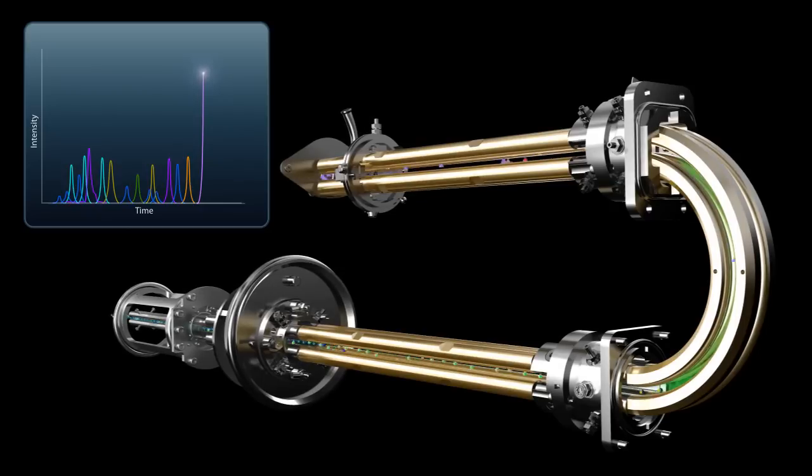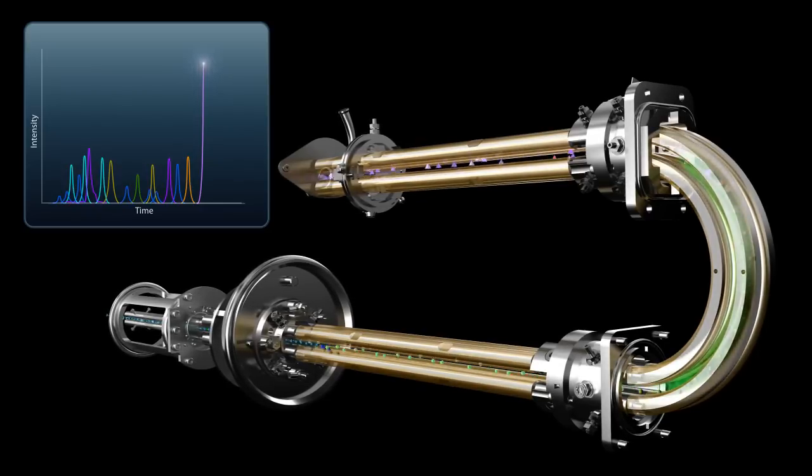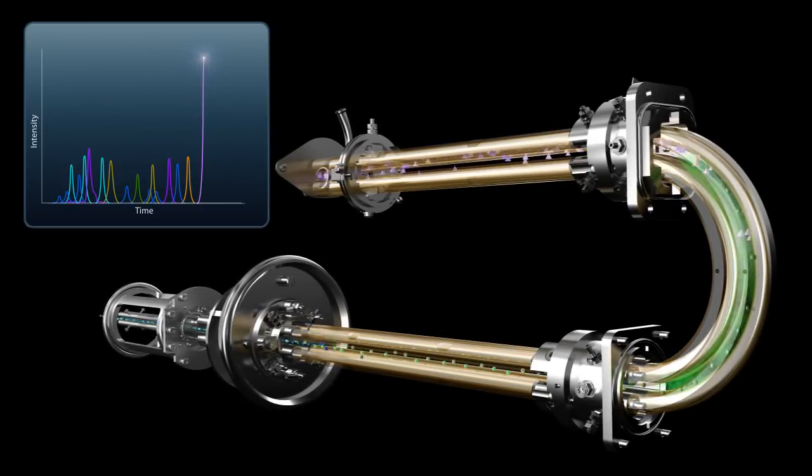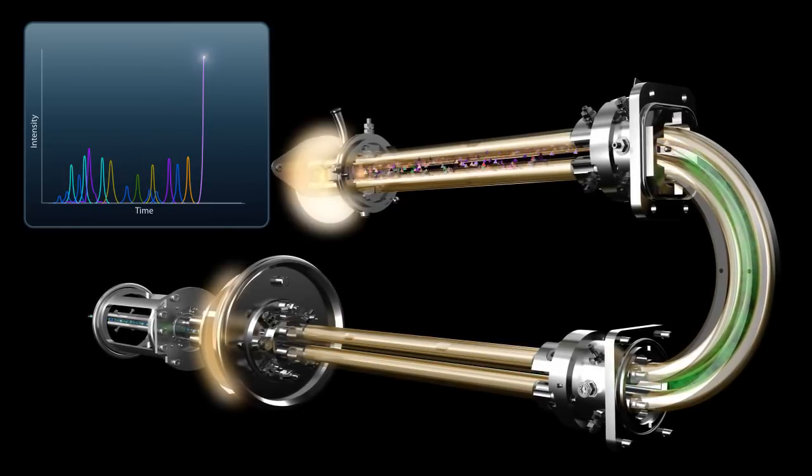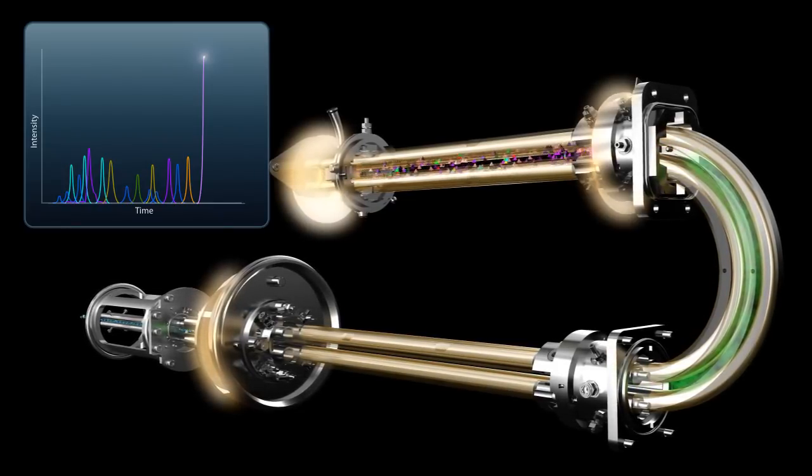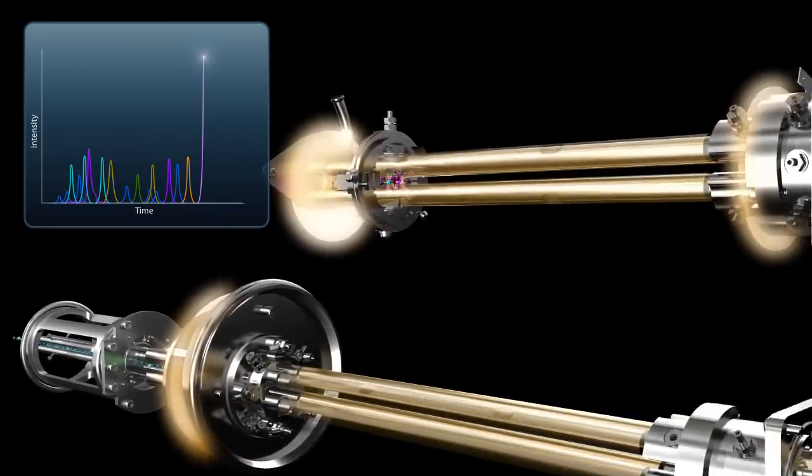But uniquely, when a specific MRM transition is detected, Q3 can automatically switch to linear accelerator trap mode in less than one millisecond to deliver high-sensitivity full-scan MS-MS data.